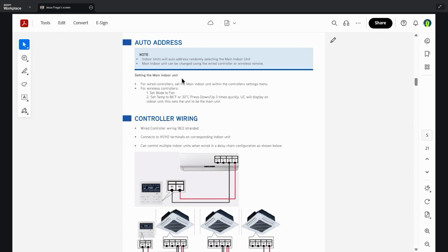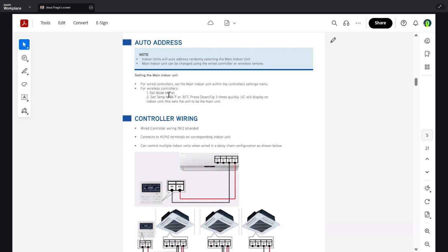So the setting of main indoor unit, as I stated, you can go to the wired controller that you choose to be the main indoor unit and actually designate that system for main indoor unit operation. What this means is this main indoor unit will be the only unit that will be able to change the mode from heating to cooling and vice versa. If you try to go to any other controller in the system, you will not be able to do that. You won't even get the selection of the opposite mode that the unit is in on the subordinate controllers.